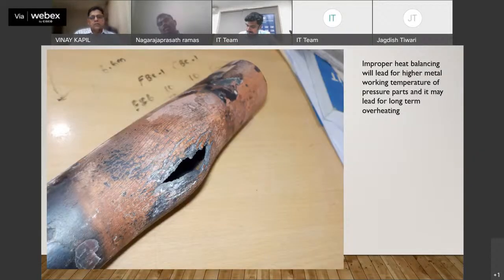This type of superheater tube overheating failures was faced in the superheater zone. Earlier the LT superheater outlet material was T11, and we calculated the metal working temperature as crossing 510 or 520 degrees Celsius. We changed only the superheater outlet tubes to T22, about one year back, after which we did not face any problems. Unfortunately, the earlier materials also ran 6 or 7 years of operation, so we are waiting to see what the result will be after 6 or 7 years of operation.